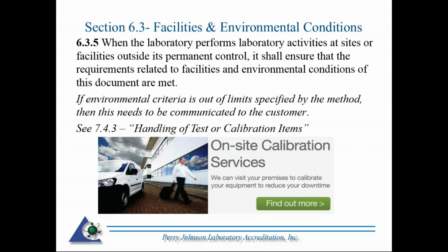I also referenced here section 7.4.3. So often, if I can speak on behalf of calibration activities that I witnessed, with the tight conditions that are maintained in the fixed facility, oftentimes those environmental conditions are not maintained off-site. This is addressed also in section 7.4, the handling of test and calibration items.